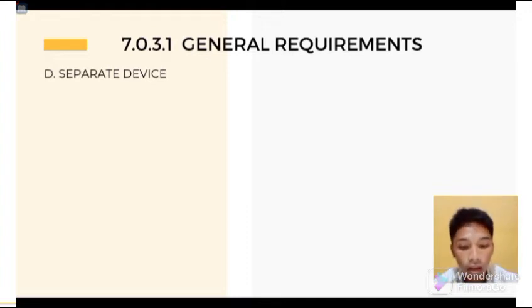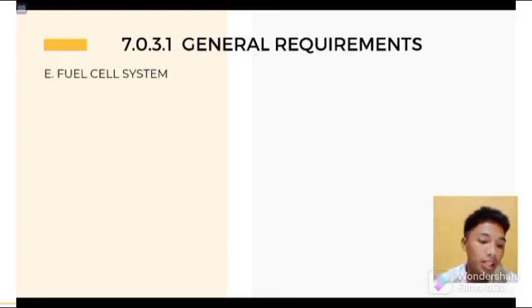Number 2, service conductors sufficiently remote electrically and physically from any other device or any other service conductors to minimize the possibility of simultaneous interruption of the supply. Letter E, fuel cell system. Fuel cell system used as power source for emergency systems shall be of suitable rating and capacity to supply and maintain the total load for not less than 2 hours of full demand operation.